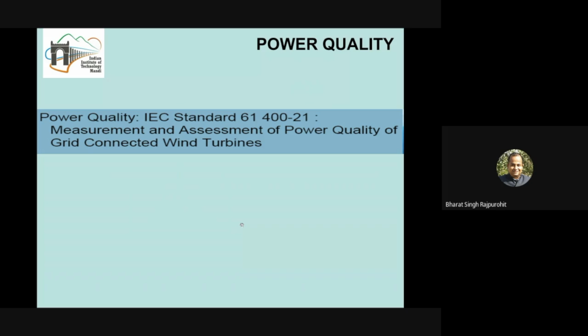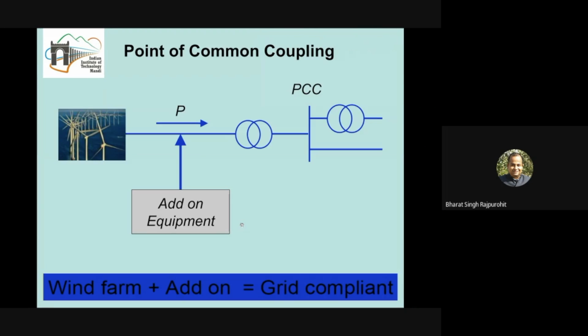The grid code expects that a power quality standard as per IEC 61400-21 should be followed, and that the wind turbines maintain the power quality at the point of common coupling. So in a broader sense, whatever grid connection requirements we have discussed, it is expected that the wind farm or solar farm should be able to meet them at the point of common coupling by having technological enhancement in themselves.